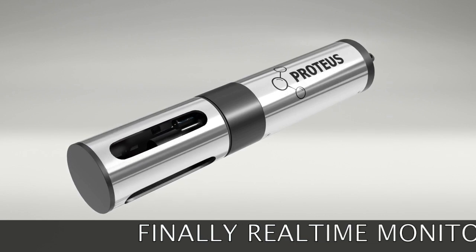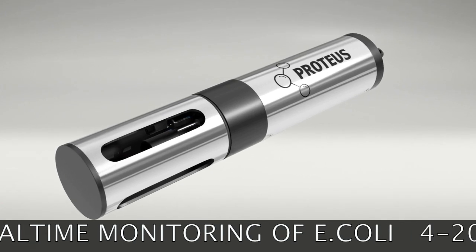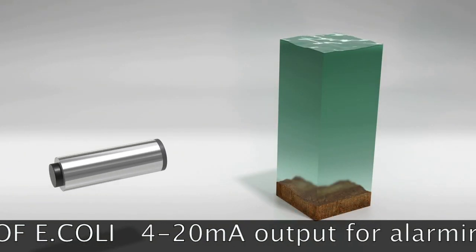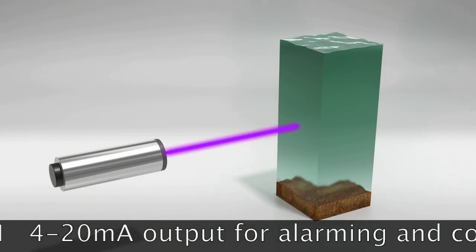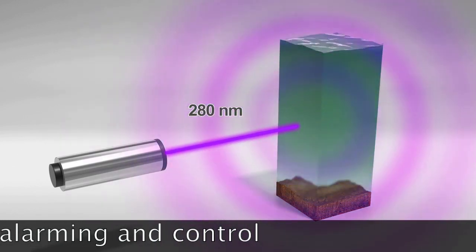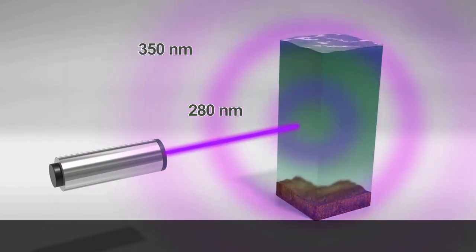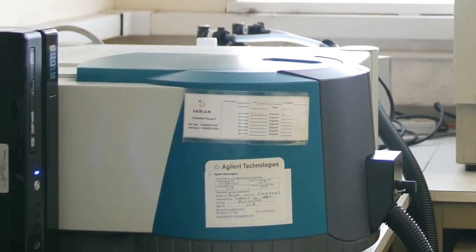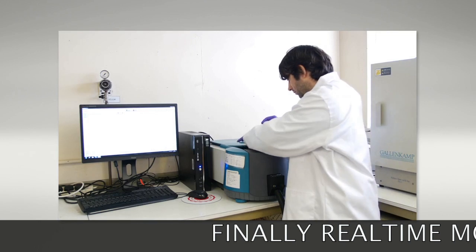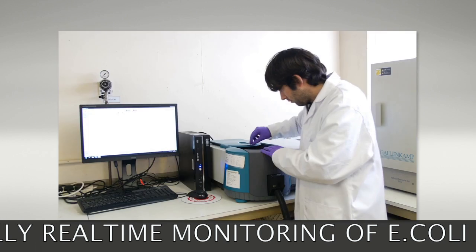A global scientific breakthrough in providing low cost, real time data for BOD, COD and faecal coliforms. What's the secret? If you hit waste organic material with a short ultraviolet wavelength, approximately 280 nanometres, it'll fluoresce at a particular wavelength, approximately 350 nanometres, which you can use to measure BOD. These fluorometers have been used for many years in laboratories for analysing water quality samples from the field under the established and trusted technique for reliably measuring dissolved organic matter.